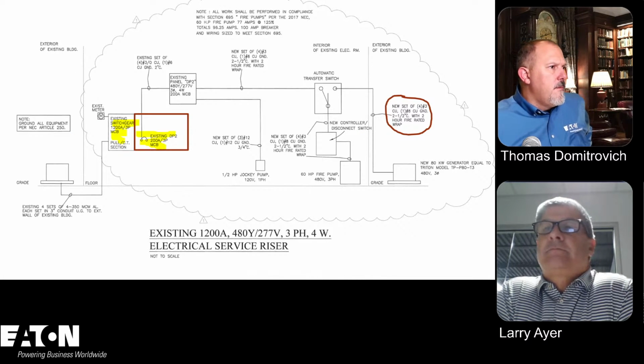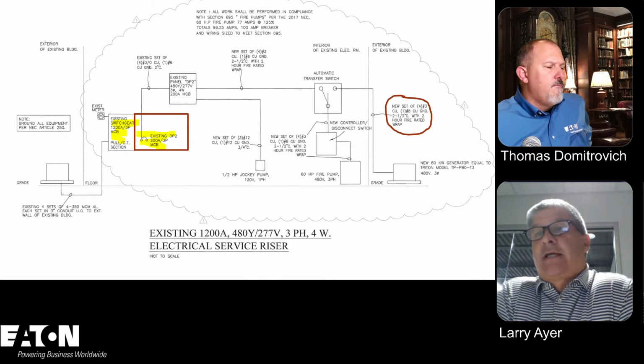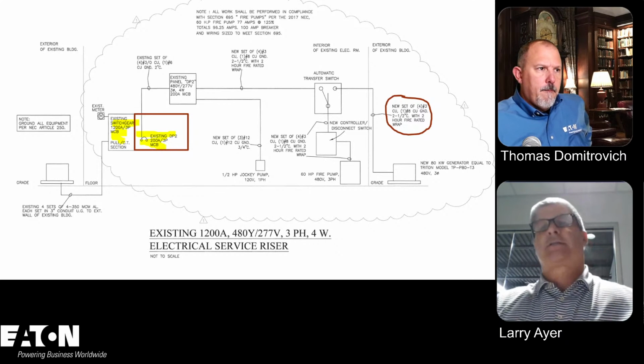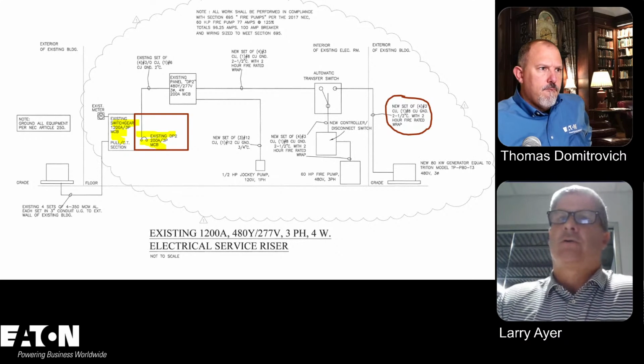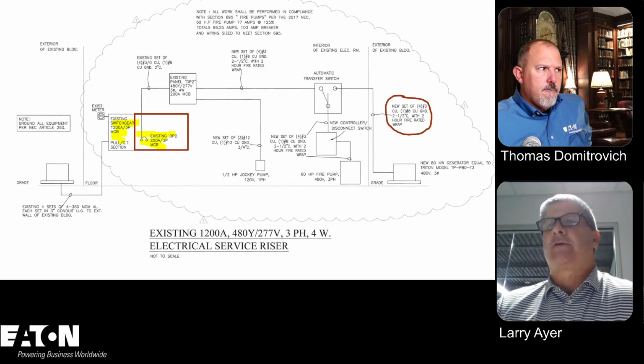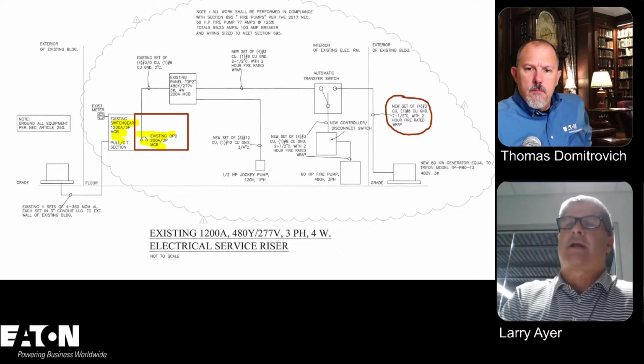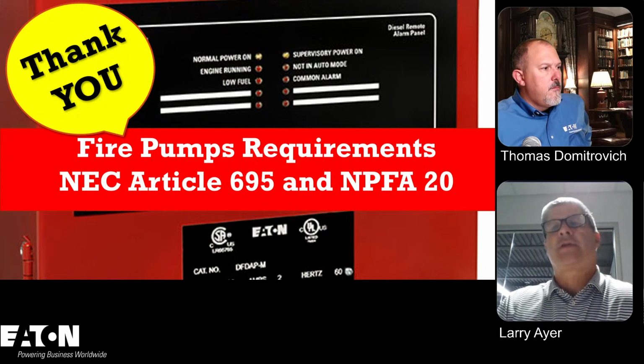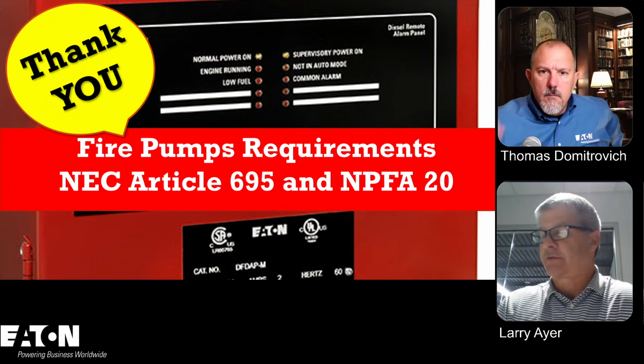Excellent. Now the other thing is you got to make sure that's an 80 kW generator, and then you've got a 60 horsepower fire pump. So you need to make sure. A lot of times what I do is I send these things to my local vendor for generators, to make sure that generator is capable of starting up the fire pump with no problem, within the parameters of voltage drop.